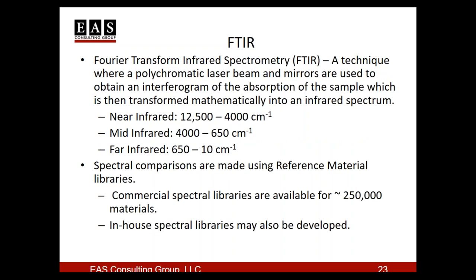FTIR, like we talked about, is Fourier Transform Infrared Spectrometry. This technique uses polychromatic light, multiple light ranges with a laser beam, and mirrors that focus to obtain what's called an interferogram of the absorption of the sample. That's then mathematically transformed into what we see as an IR spectrum.